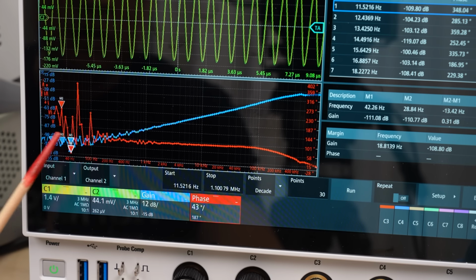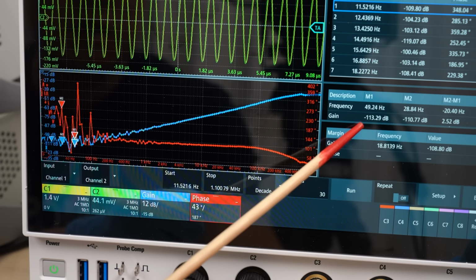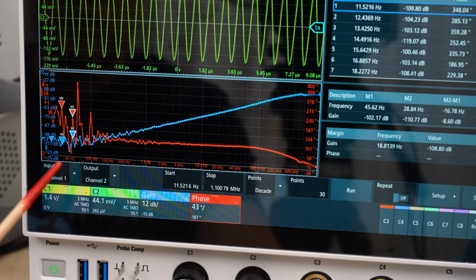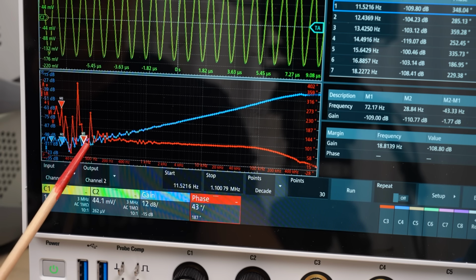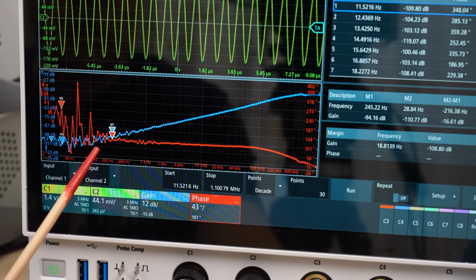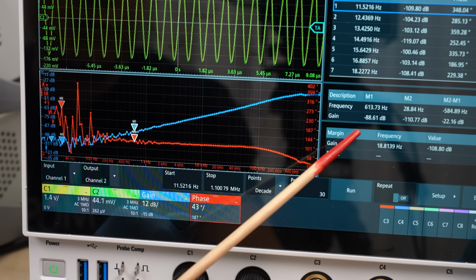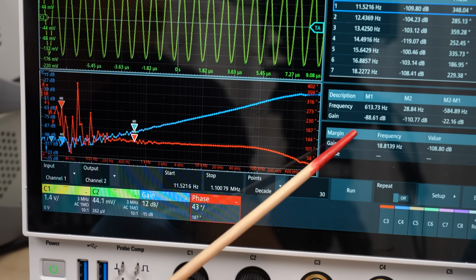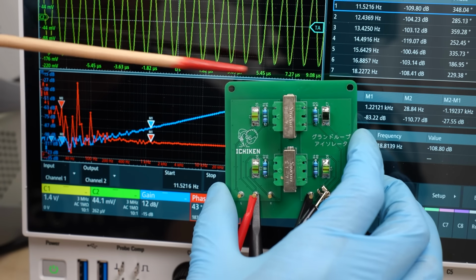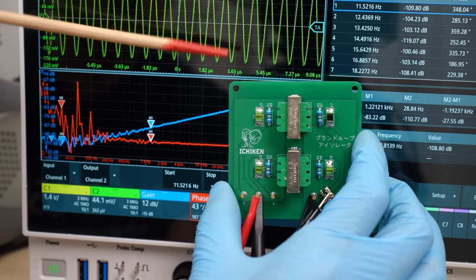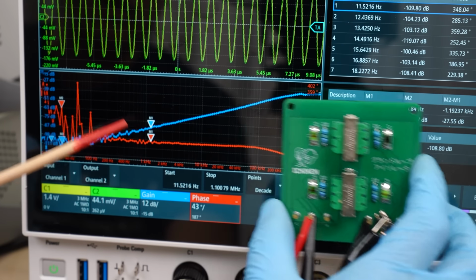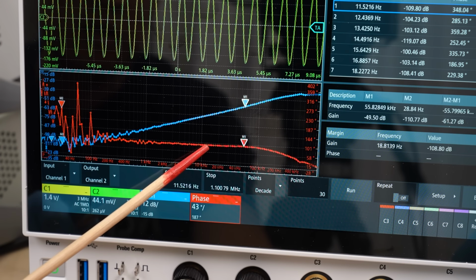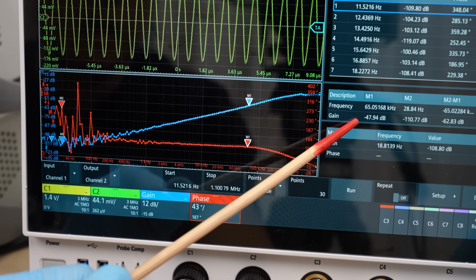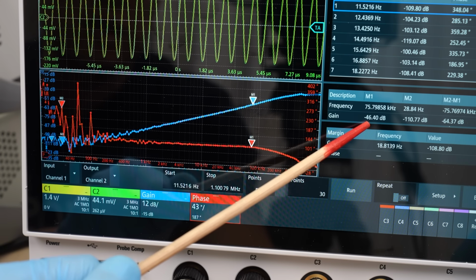At lower frequencies, it's around 100 dB, so the ground loop noise is being eliminated quite well. This indicates a high common mode rejection ratio. But as the frequency increases, beginning at around 100 Hz, ground loop noise starts to appear at the output. As I mentioned earlier, this is the signal passing through the capacitance between the transformer windings. That's what's causing the noise. As the frequency increases, ground loop noise leaking through to the output side of the transformer gradually begins to appear.